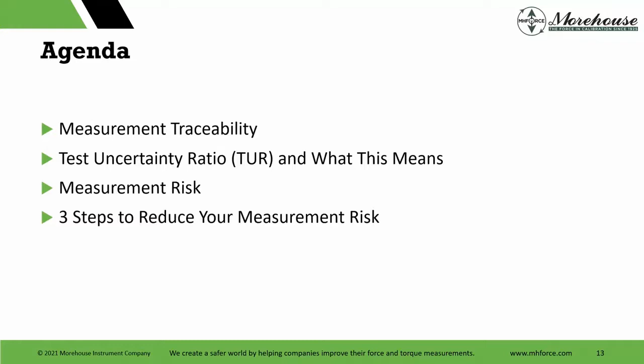Those that saw the video know that this is the metrological traceability chain. The video showed that. But when measuring force, the load cell should be calibrated using measurement standards traceable to the SI through an NMI, National Metrology Institute. They are recognized under the CIPM MRA, and that recognition is necessary as some NMIs cannot provide traceability. So if we go to NIST, NIST says metrological traceability requires the establishment of an unbroken chain of calibrations to specified reference standards, typically to national or international standards, in particular realizations of the measurement units of the International System of Units. NIST assures traceability to SI.